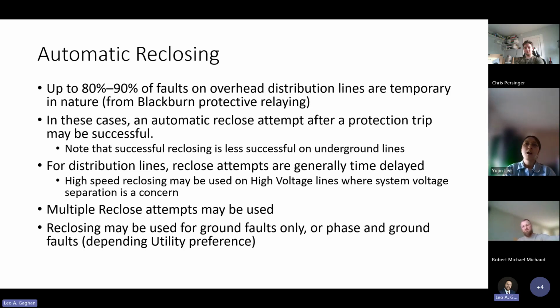Reclosing is also much less successful, typically for equipment in the substation, like the transformer and the bus work in the substation. That's just because you're not going to have vegetation inside the fence of that substation. You're going to be within lightning protection, so lightning's not going to cause it. Usually if it's in the substation, unfortunately, it might be personnel, like a boom lift. So everything we're talking about is going to be, think overhead distribution lines.